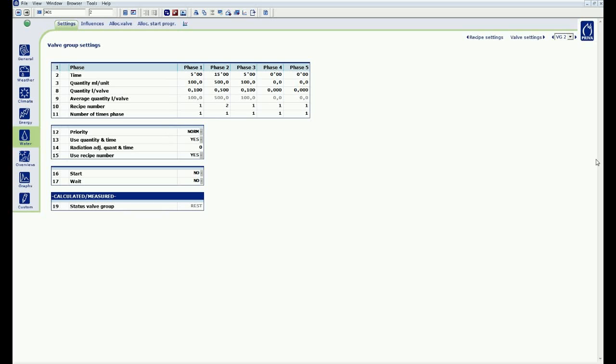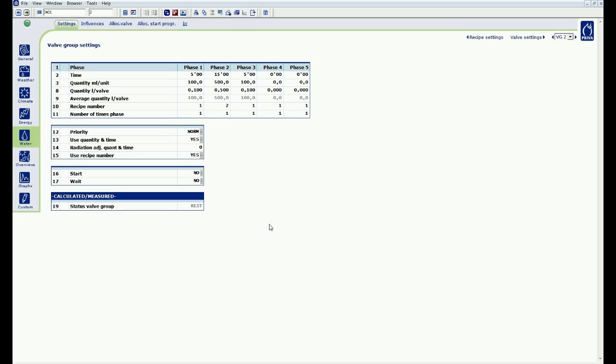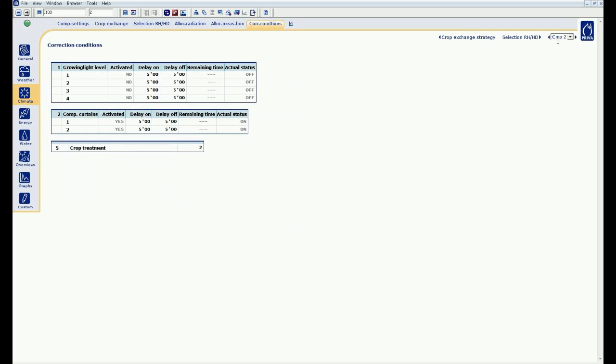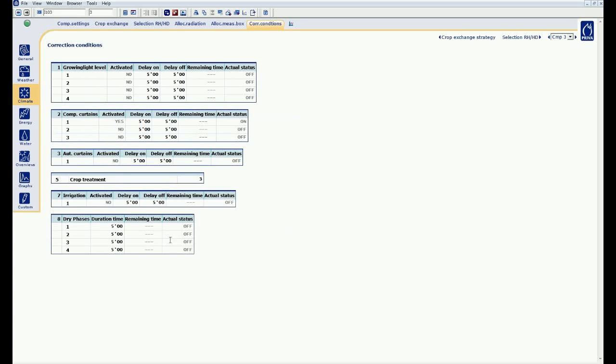I want to make the correction in compartment 3, which is linked to valve group 2, based around a manual start. In the menu, I go to climate, general, correction, conditions. I am going to the corrections of compartment 3. In this page you will find a number of installations to which I can correct with a condition. You will also see the status of the installation at this time, and you will see delay on and delay off.